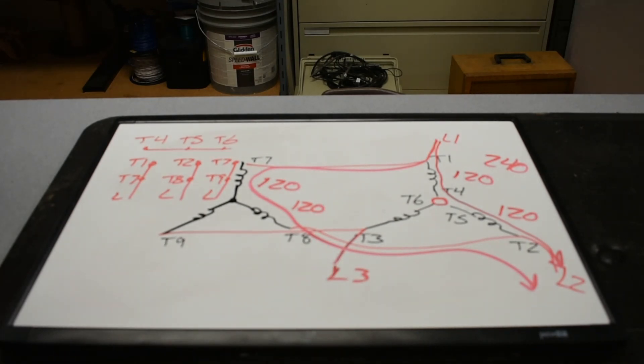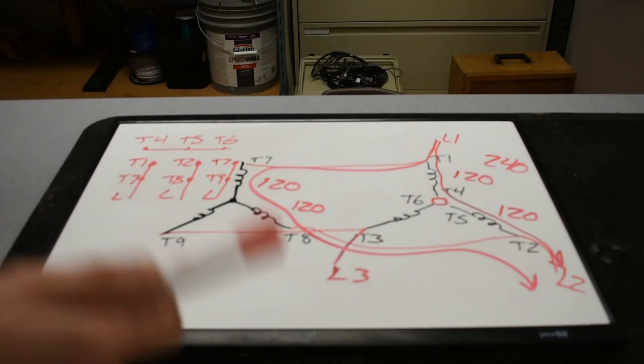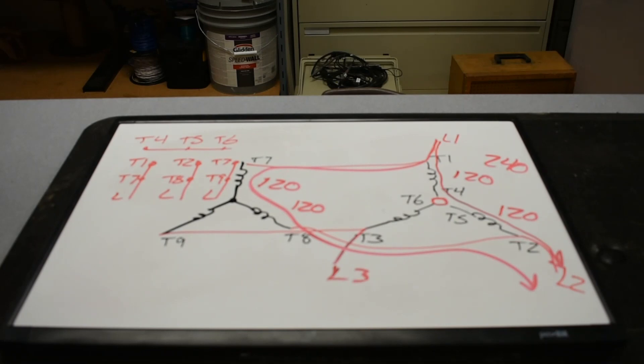If you have a motor that's wired for 480 and you connect 240 to it, you won't be at risk of damaging the motor, but it's not going to operate because each one of those coils that was expecting 120 is only going to be getting half the amount of voltage. Therefore, it's going to be generating a lot less power and you probably won't even see the motor rotating at all. It's just going to be too weak. So definitely never hook up a low voltage winding motor to a high voltage source. Big no-no there.